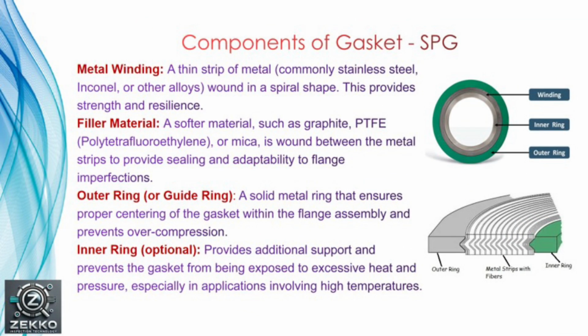So after seeing the MOC, material of construction, now we will come to the topic components of the gasket. So there are four components. One is metal winding, other is filler material, one is outer ring or guide ring, and inner ring, that is optional. So basically, metal winding is a thin strip of metal, commonly stainless steel, Inconel or other alloy materials. It is wound in a spiral shape. This provides the strength and resilience. You can see in the picture there are three parts: winding, inner ring and outer ring. So winding consists of filler material and metal winding.